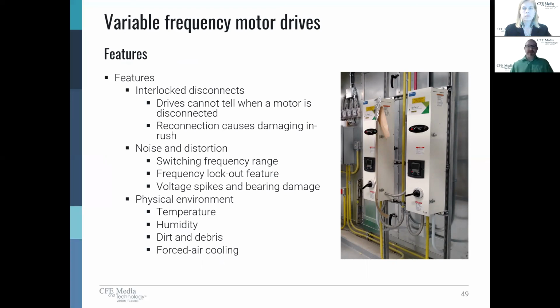Now, anytime I use a VFD, I'm going to make sure I put it in the right spot. I tend to not put these things outside. They can get hot, they can generate heat, and more importantly, they're very sensitive electronics. So we want to be fairly careful about their application and ensure that when I place a VFD in a location, it's not going to fail prematurely simply because it's too hot. Now, many VFDs have a lockout range, in which case you can say if I have a problem frequency, I can actually stop that frequency from being generated throughout its range. Maybe it skips 57 hertz. And that might be because 57 hertz generates a really problematic vibration.